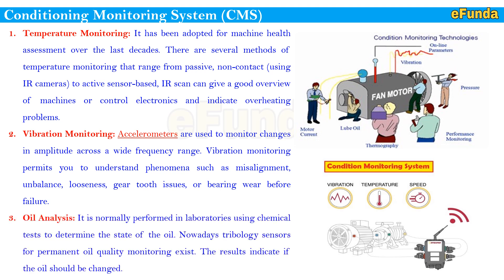Third and most critical is oil analysis, normally performed in laboratories using chemical tests to determine the state of the oil. Tribology sensors for permanent quality oil monitoring now exist. The results indicate if the oil should be changed. This technology is more focused on determining the condition of the lubricant — that is its viscosity, basicity, etc. Oil level and quality tracking are very important to prevent costly repairs. This is how condition monitoring system is used for measuring temperature, vibration, and oil analysis.